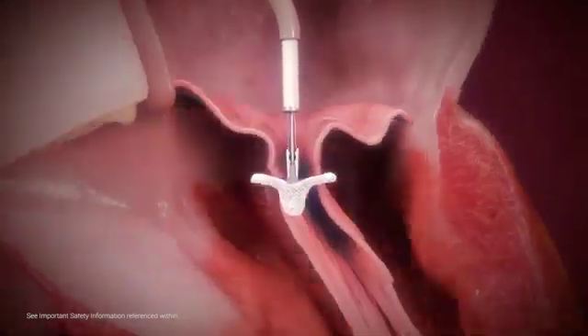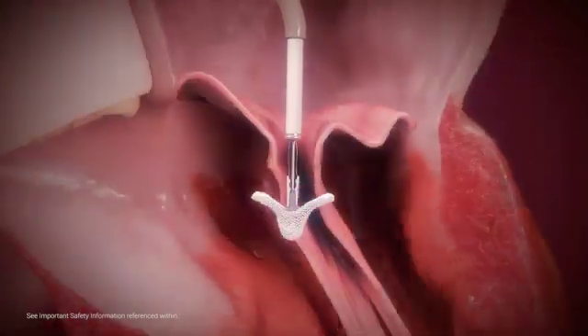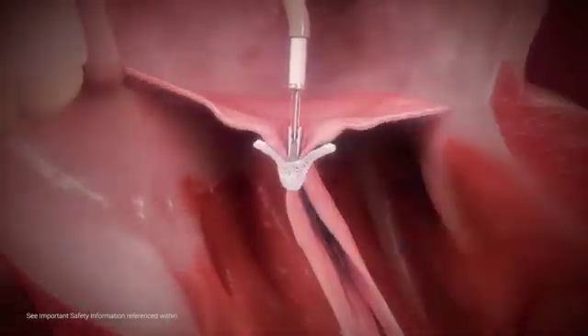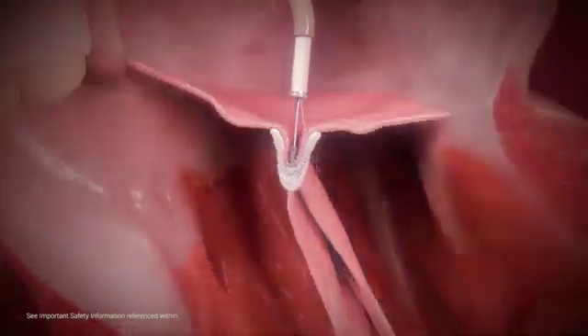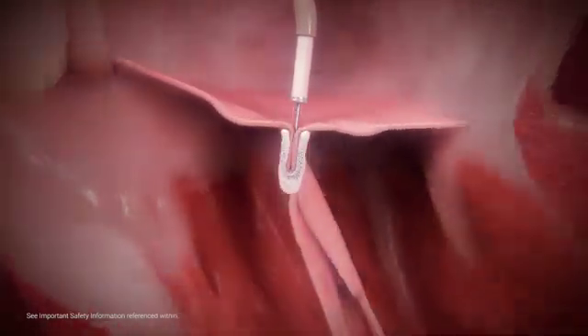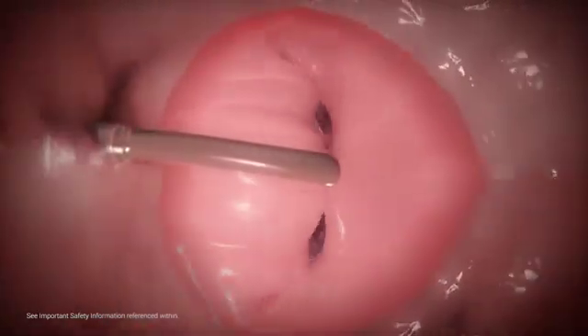The clip is advanced into the left ventricle, below the valve leaflets, and retracted to grasp the leaflets. MitraClip grippers are designed to drop firmly into the clip arms, securely capturing both leaflets. Once the arms are closed, they create a double orifice within the mitral valve.